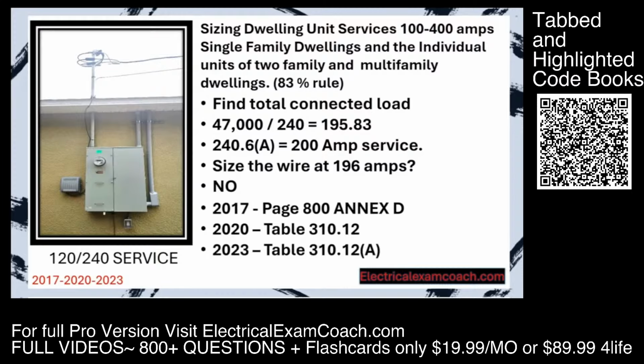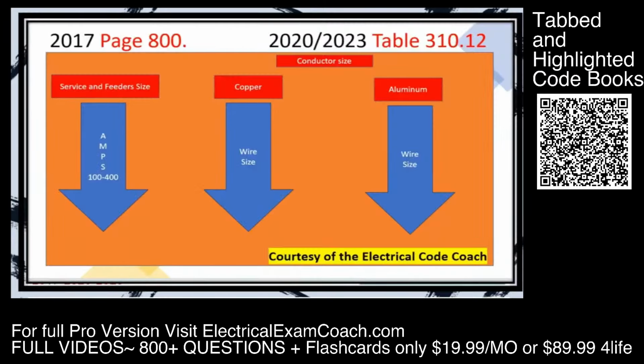This is technically called the 83% rule, but I'm not going to force you to do the longhand math. I'm going to take you to these tables in the NEC that are almost like a cheat sheet that makes this super easy to apply and understand. Let's get to it. Once we get to our table, we work all of our tables from top to bottom, left to right, using those headings to navigate the table.